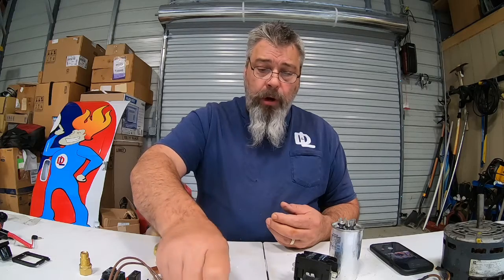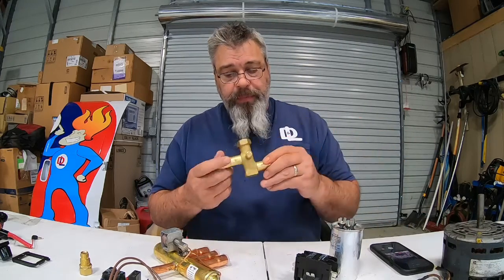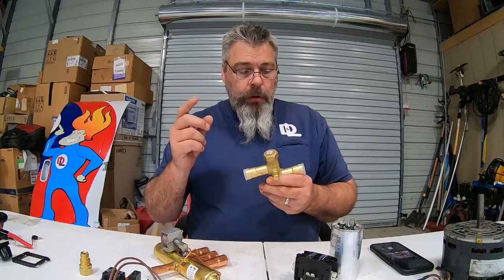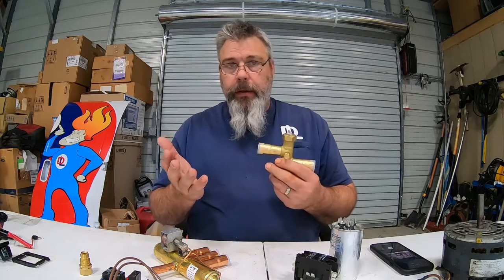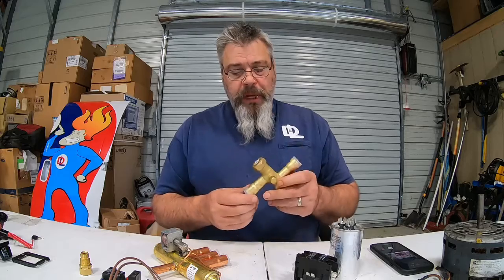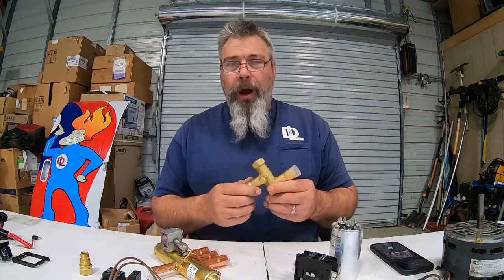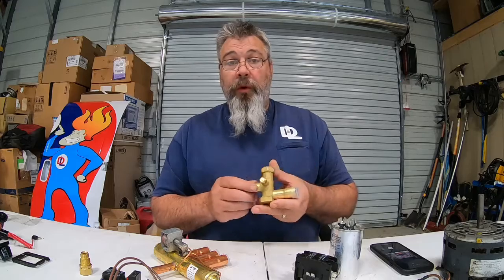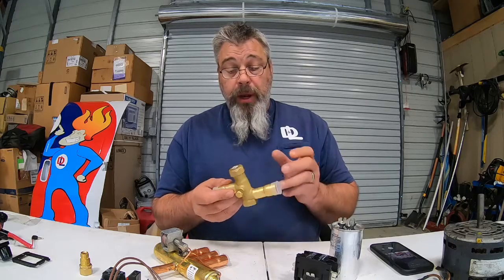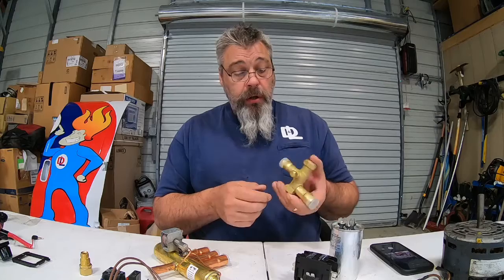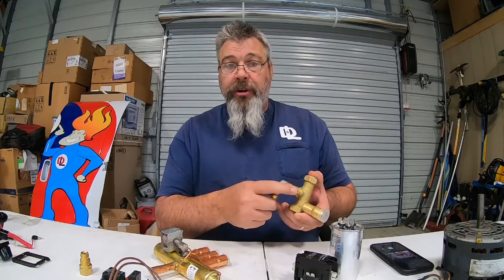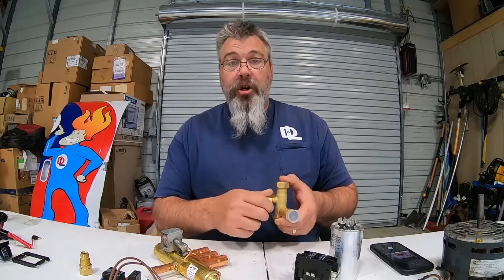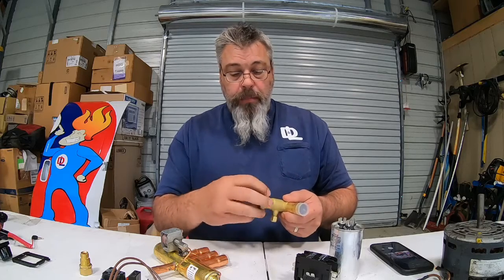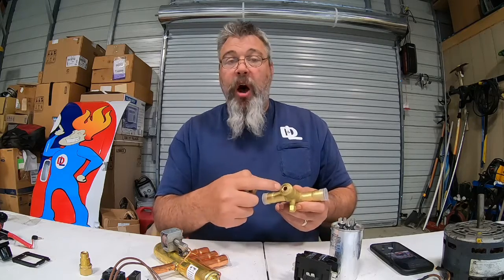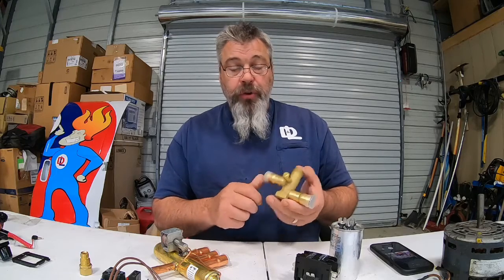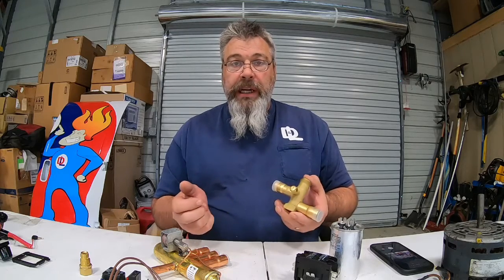The next component that I want to talk about is a service valve. Service valve, king valve, it takes on a lot of different names. Is there really much you should know about this? No, not really. Basically, this is more for the manufacturer, for the technician. What they put these in here for is servicing. We have a port that comes out here where we connect our gauges. We are able, as service technicians, to open this up and close a valve down if we have to. We actually use these to test systems for leaks.